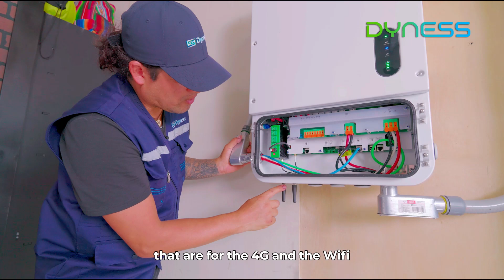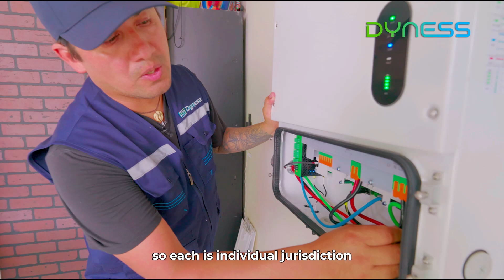All right guys, we're going to go through the AC connections. What we're going to be doing here and what you're going to see here is the connection points from the inverter hybrid to the actual smart controller. So each individual jurisdiction, make sure you get in contact with your AHJ for what is line 1, neutral, and line 2 colors. In this case here, your line 1 is black, line 2 is red, and your neutral is white. Same scenario, you'll gently pull up the tab, insert the wire at the proper requirement length of stripping back each individual wire.